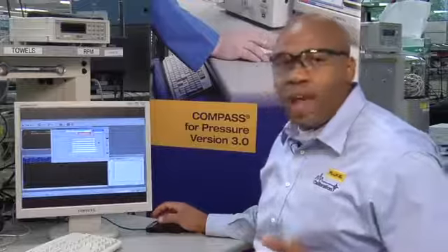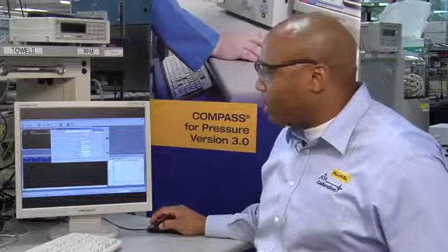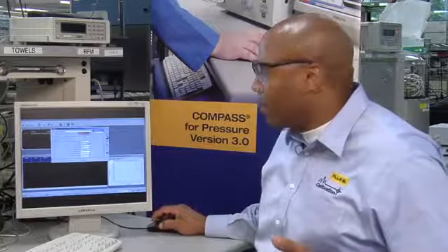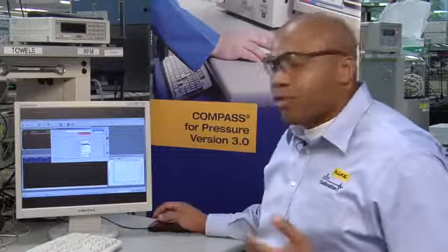So most instruments don't have such a complicated setup. So a more typical example is when you create the instrument, you of course have to identify it, but for communications, macro is rare. Typically it's RS-232 or IEEE 488 or one of the other standard interface protocols. So IEEE is a more common remote interface choice. If I pick IEEE, I can define the specific address, an acceptable timeout, how the device communications are terminated. More importantly though, I can define all the specific remote interface commands for IEEE.